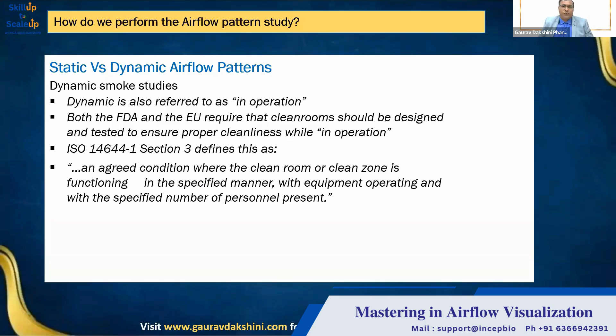So that's when the requirement will be fulfilled. Static means you are not running the product online - majorly you use it to qualify the HVAC. Dynamic is an actual simulation of your product, where you run the actual run, of course with WFI water, not with the product.